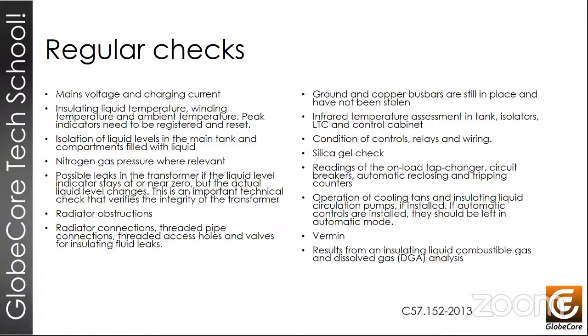So these inspections, daily inspections, are very important for keeping the transformer in good working condition. This list of preventive inspections in the standard C57.152-2013 is quite extensive. Often what we don't do is check voltages and currents. For example, at one point, overheating of power lines was caused by excessive load due to not knowing these values. Other important things include checking the temperature of the insulating oil and the level of the insulating liquid in the transformer.